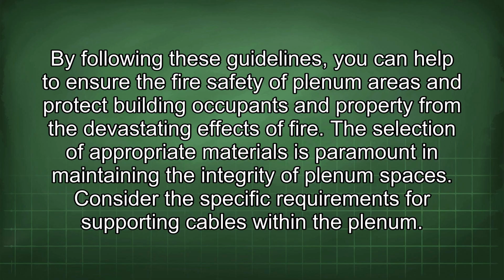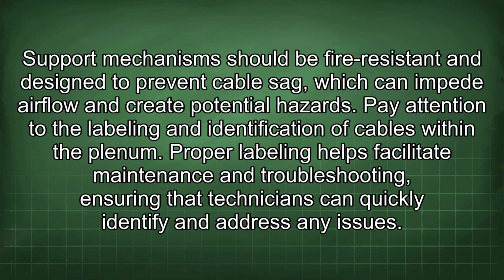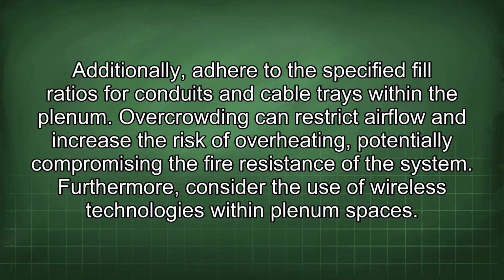The selection of appropriate materials is paramount in maintaining the integrity of plenum spaces. Consider the specific requirements for supporting cables within the plenum. Support mechanisms should be fire-resistant and designed to prevent cable sag, which can impede airflow and create potential hazards. Pay attention to the labeling and identification of cables within the plenum. Proper labeling helps facilitate maintenance and troubleshooting, ensuring that technicians can quickly identify and address any issues. Additionally, adhere to the specified fill ratios for conduits and cable trays within the plenum. Overcrowding can restrict airflow and increase the risk of overheating, potentially compromising the fire resistance of the system.